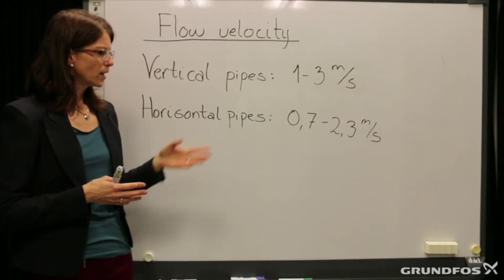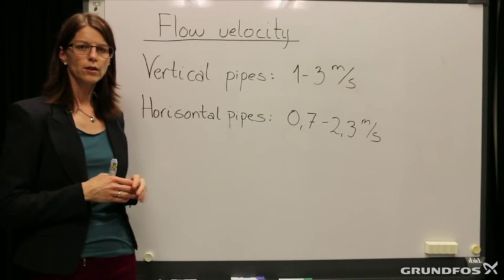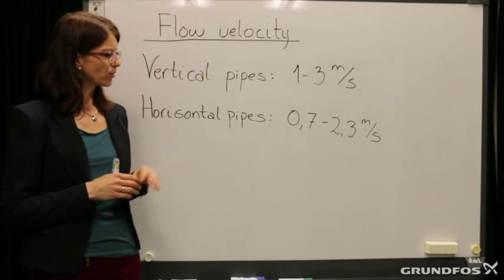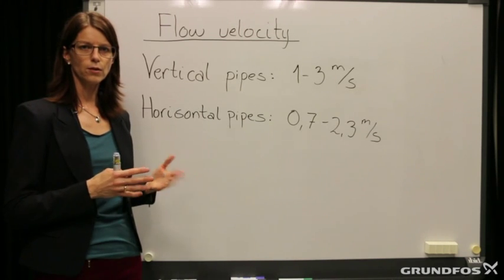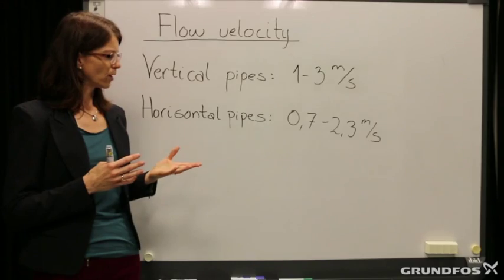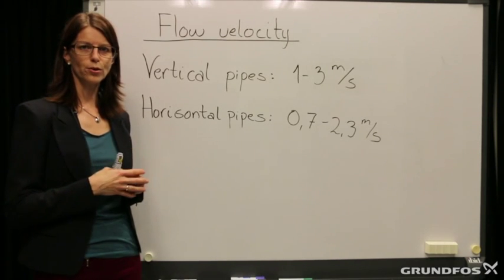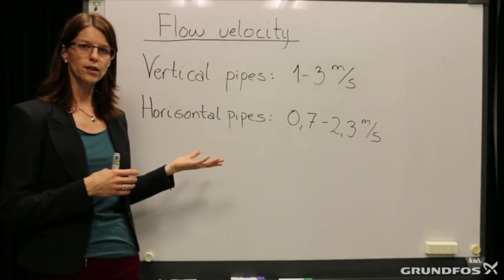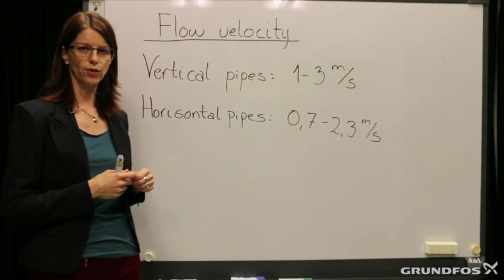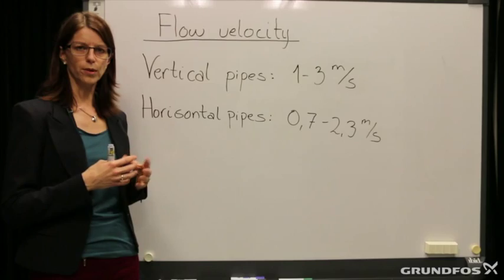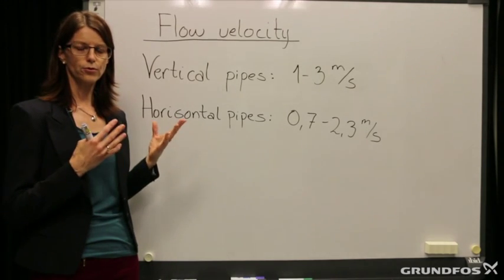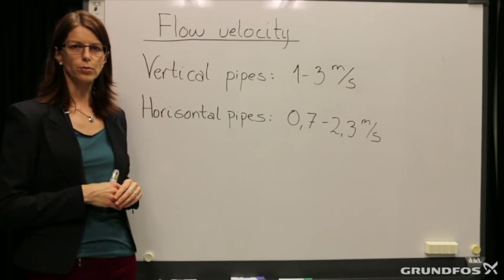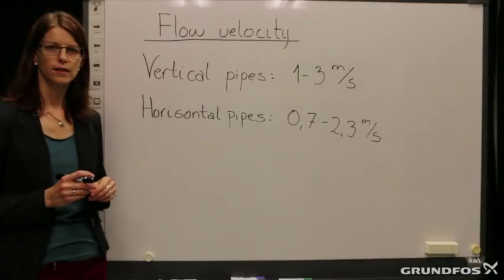We also want to avoid the velocity being too high, so the upper limitation is about 2.3 meters per second. The reason is that the wear of the pipes will increase when the velocity increases — there will be more noise, and also a very important economical factor: when the flow velocity increases, you also have increased friction, and thereby you need a bigger pump to pump the flow. From an economical point of view, flow velocity should be kept below 2.3 meters per second.